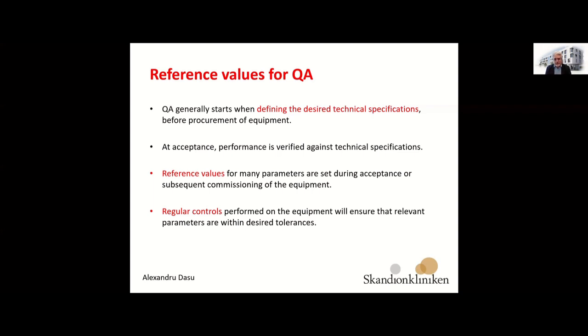Now, after the procurement and the installation of the equipment, you usually go through the acceptance. And at acceptance, you verify that the performance of the delivered equipment corresponds to the technical specifications that you put in the procurement. And actually, many of the reference values for the parameters that you are going to check are set during acceptance or the subsequent commissioning of the equipment. This is where you say, well, I want my equipment to continue performing at this particular level. Now, after you have said this, you perform regular controls, and they will ensure that the relevant parameters are within the desired or the recommended tolerances.